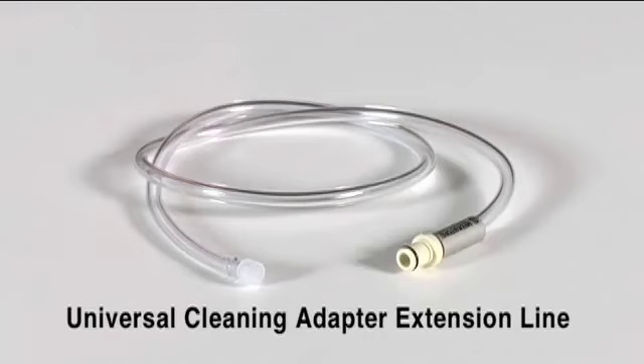Universal Cleaning Adapter extension line. This extension line is used by facilities without a Medivators DSD endoscope reprocessor. This extension line snaps into the out port on the Scope Buddy unit and, in conjunction with the multi-way adapters, allows connection to the endoscope's channel irrigation adapter supplied by the endoscope manufacturer.